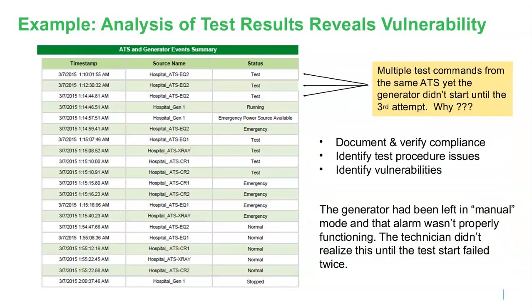Another very important part of the reporting is the sequence of events, showing you a summary of everything that occurred and when it occurred. And here's a quick example that raised a flag real quick. Where I'm showing, the first 3 events were test status from the same ATS. So in other words, the technician went up to the transfer switch and attempted to initiate the test there 3 times before the generator started running.